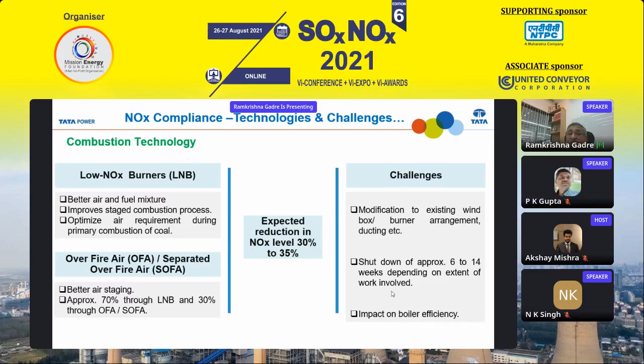I'll quickly go through the NOx issues. I know SOx has been the focus here, but everybody most probably already has low NOx burners and overfire air. What is newly required to meet the 450 norm is installing SOFA, which may give the reduction required from today's level of maybe 700 down to 450. This may depend on plant to plant, because SOFA requires additional ducting and additional openings into the boiler, so shutdown is the main issue. Otherwise, technology-wise it's a simpler thing and can be implemented.